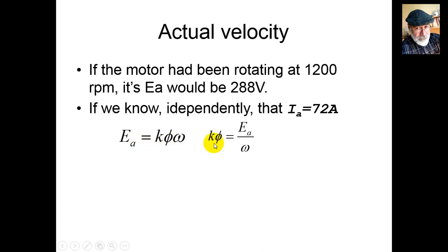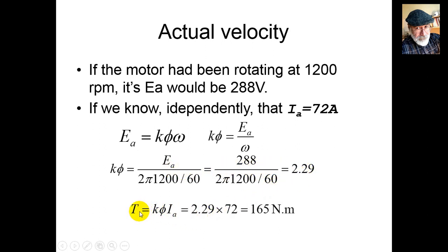Ea equals Kφ times omega. We solve for Kφ as induced voltage divided by omega. In our case, 288 volts divided by omega at 1200 RPM converted to radians per second: 1200 × 2π / 60. We get Kφ = 2.29. Then the induced torque is Kφ times Ia, which equals 2.29 × 72 amps = 165 Newton-meters.